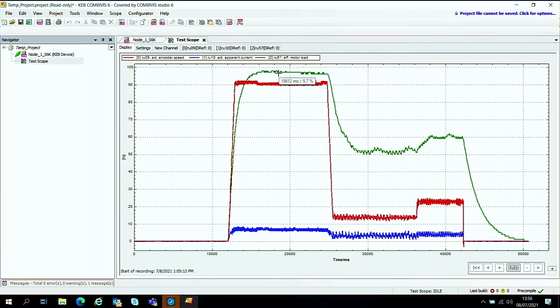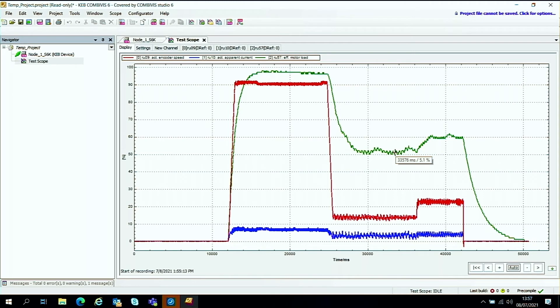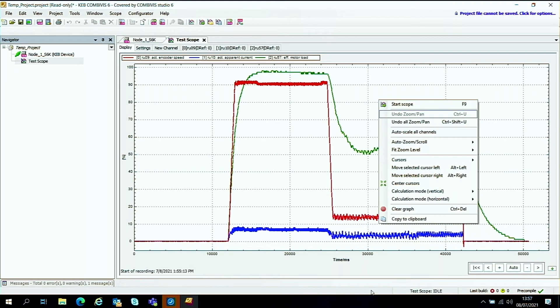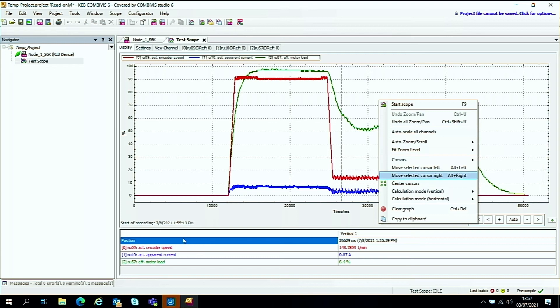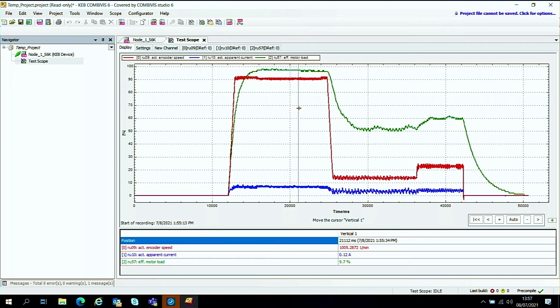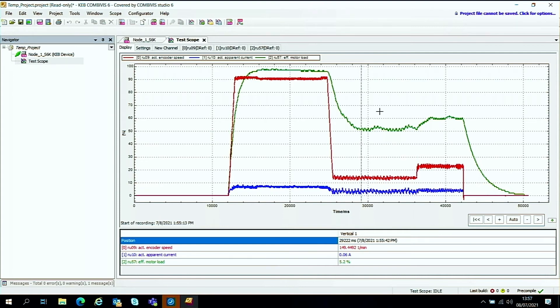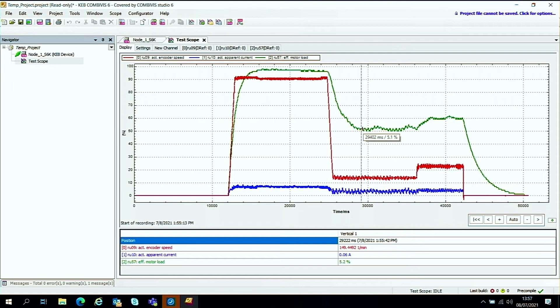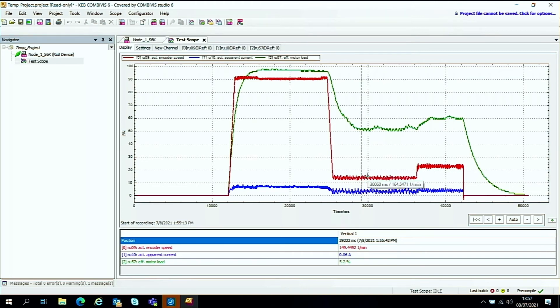So the faster it's going, it's taking about 9.8% of the load and dropped down to 5.1%. If you want to, you can go ahead and you can add some cursors. So you do a vertical one here. And you can then drag this to different areas on the scope. And you can see what different values you're getting at this particular point here. So for instance, we have 5.2% effective load. We've got a speed of 146 RPM. And we have 0.06 of an amp current.